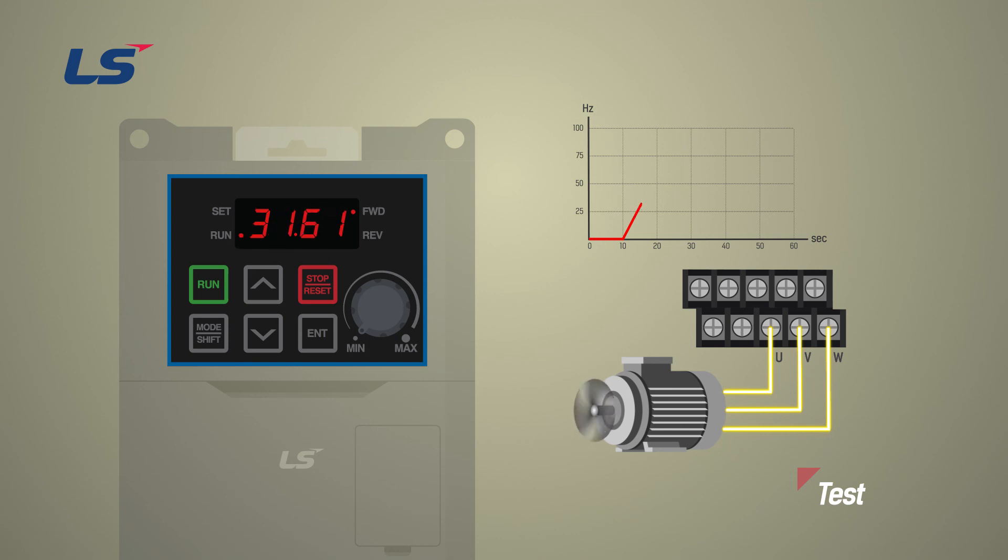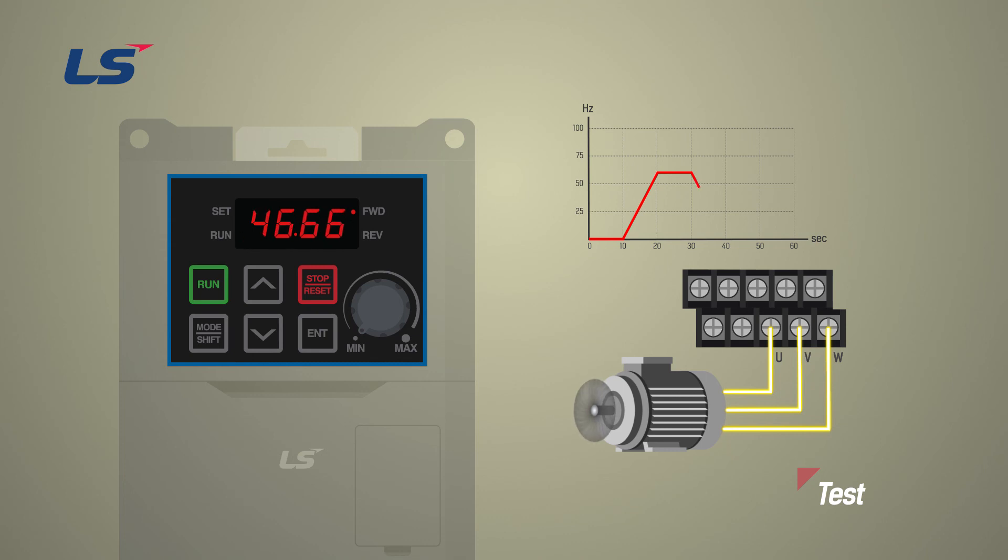If you look at the trend waveform keypad and the motor, you can see that it takes 10 seconds to accelerate from 0 Hz to 60 Hz, and 10 seconds to decelerate from 60 Hz to 0 Hz.